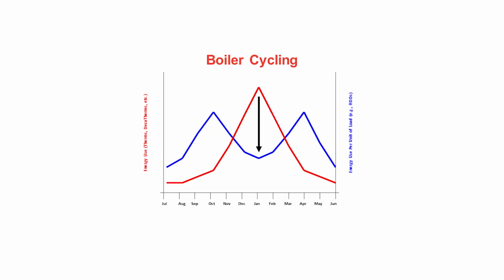This is an old boiler plant, non-condensing, think on-off, right? Because it's actually fully loaded, the boiler turns on, and it might run for 3 hours before it finally starts to overheat a little bit because there's not enough load, so it shuts down for a while, then kicks on. But the on and off cycles are really long because it's fully loaded. In the shoulder seasons, April, May, September, there's a load, but the efficiency of the boiler plant is terrible because it's cycling too much. So we have a peak design up here in the middle, and our efficiencies peak over here at the worst point, but this is where most of the operating hours are.